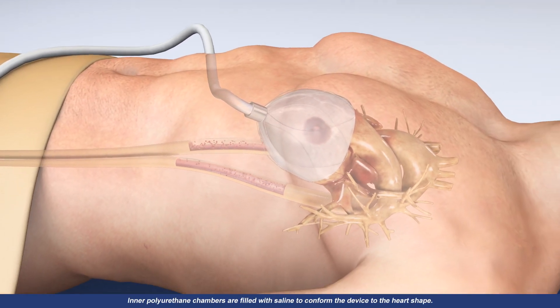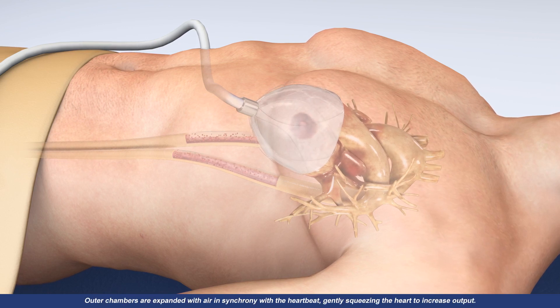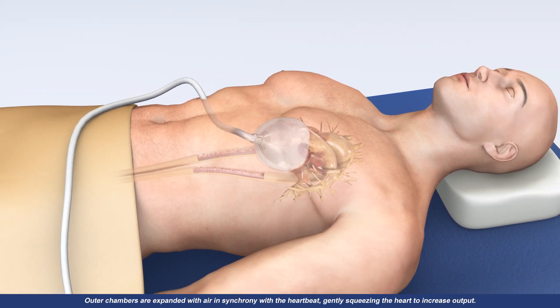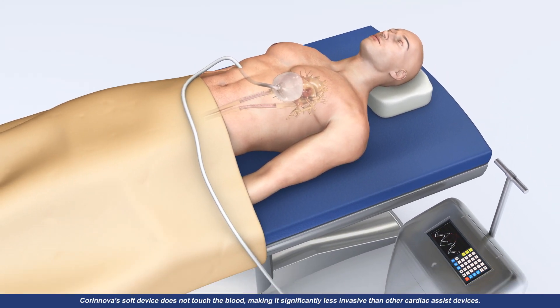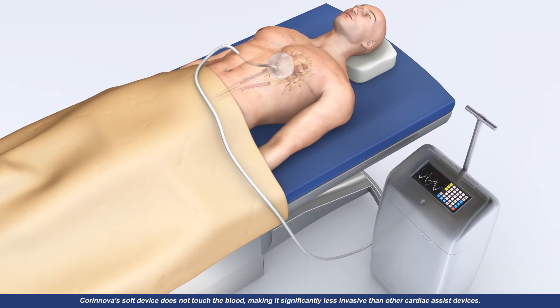Inner polyurethane chambers are filled with saline to conform the device to the heart shape. Outer chambers are expanded with air in synchrony with the heartbeat, gently squeezing the heart to increase output. CorInnova's soft device does not touch the blood, making it significantly less invasive than other cardiac assist devices.